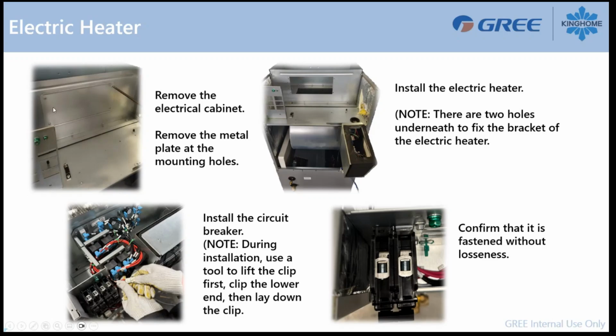Remove this metal plate at the mounting hole here in the air handler. Then you will have this section here. So you remove the metal plate, you put your electrical box aside, and now you can install the duct heater inside of it. In the back section here, you have two little holes, and the duct heater is equipped with brackets. So make sure the two brackets fit in those holes to fix the duct heater properly. This is really important. Whenever you push your duct heater inside, make sure the brackets enter those two holes in the back of the air handler.